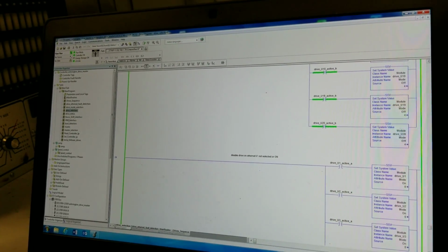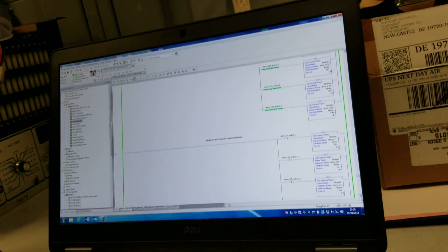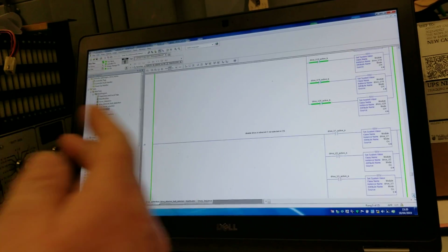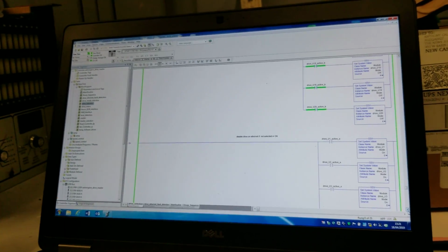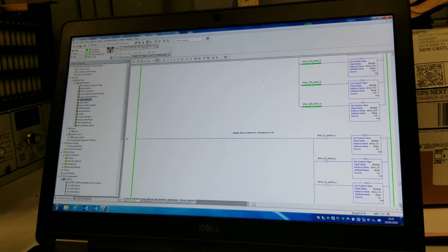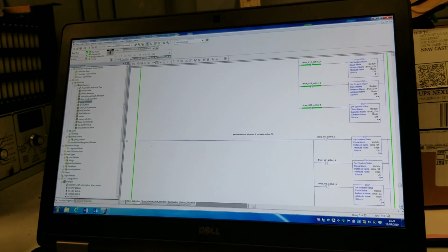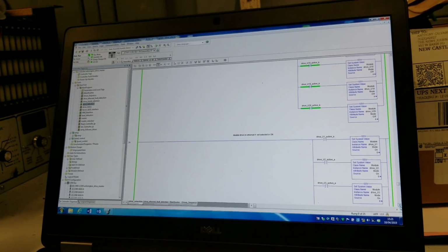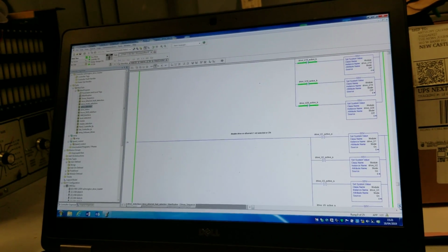This was part of our investigations of why that one didn't select. We would look at this rung and check that we are actually telling the drive to be selected to the Ethernet. We may have found that although we've selected it, we haven't made it active. Right. And that's the place to look for that. And that's what this does.